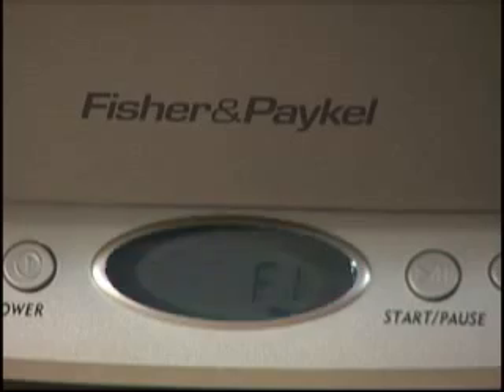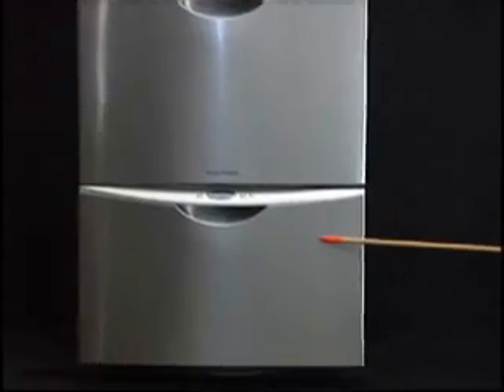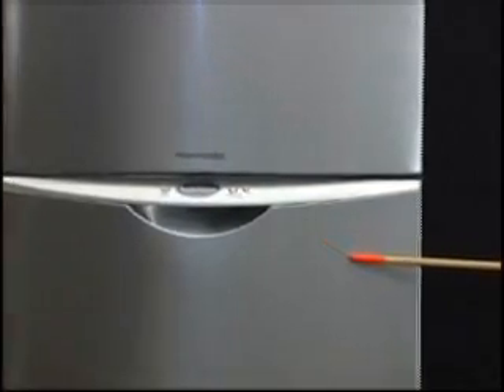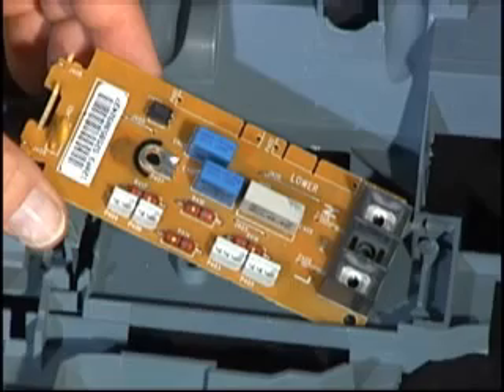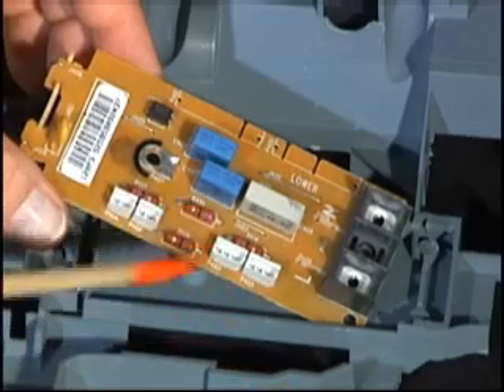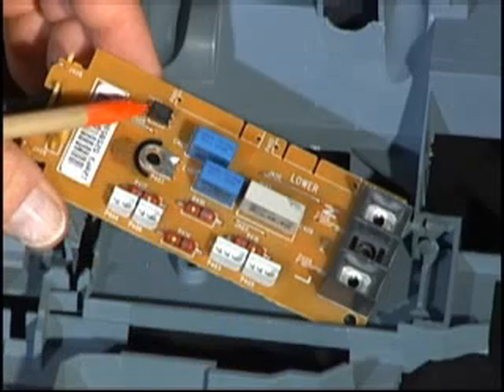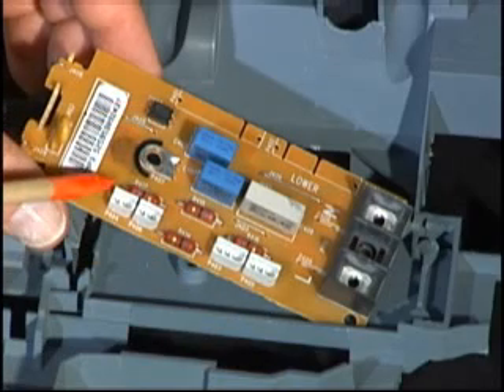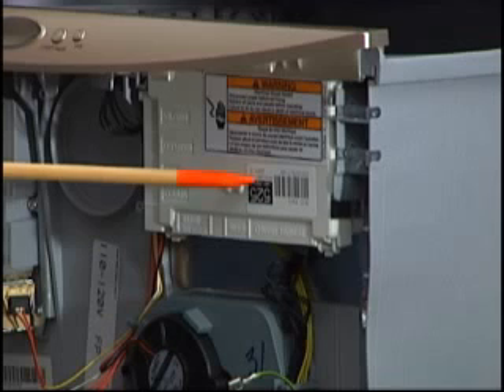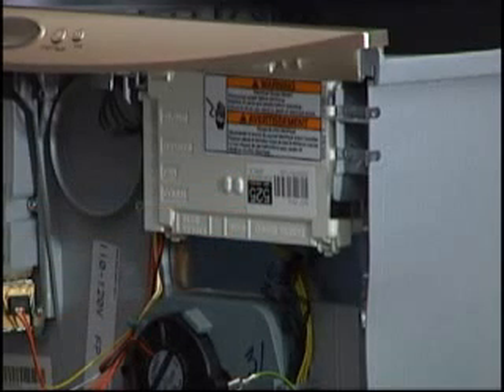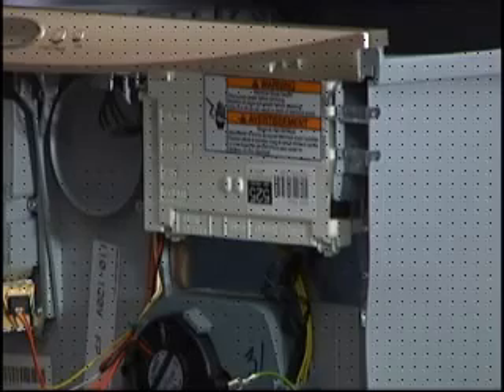When only the top drawer is giving an F1 code and the lower drawer seems to be operating, the flood sensor or lower drawer main control are the likely problems. First, check the main AC filter board for any signs of damage or burn marks. The flood sensor is monitored by the lower drawer main control board. If there is a malfunction in this board, the upper drawer can receive a false signal.